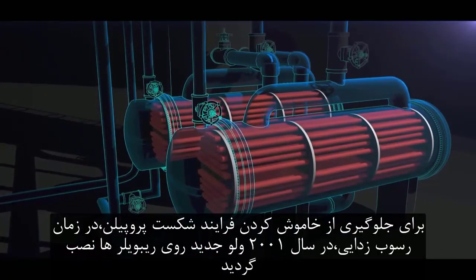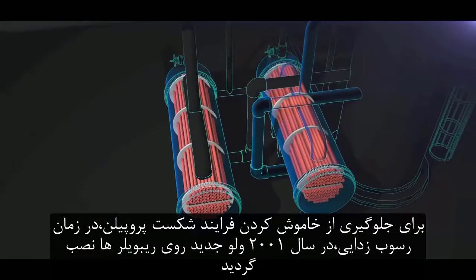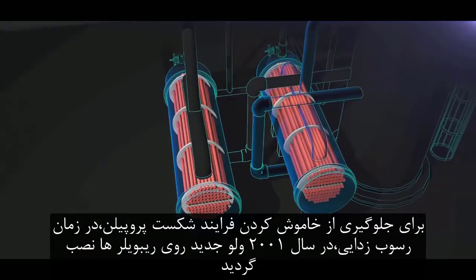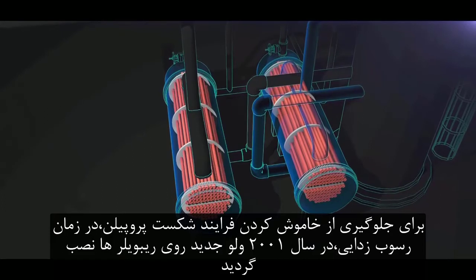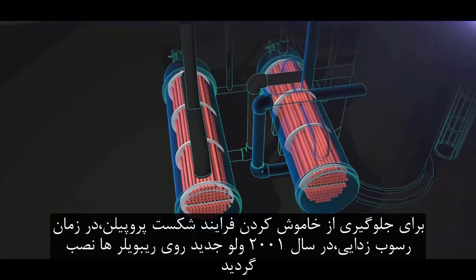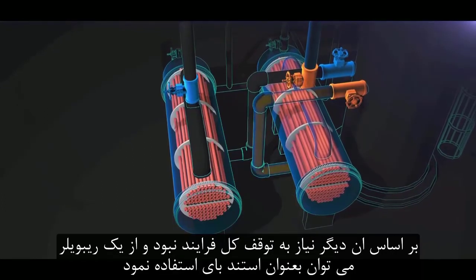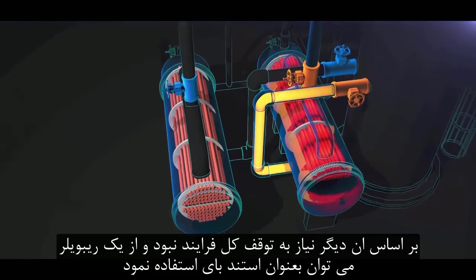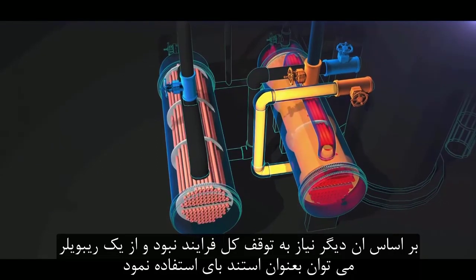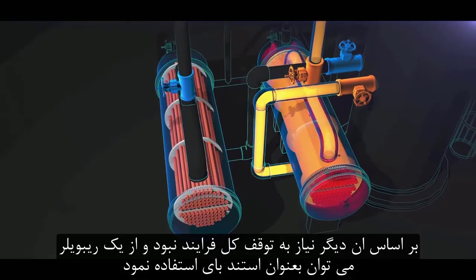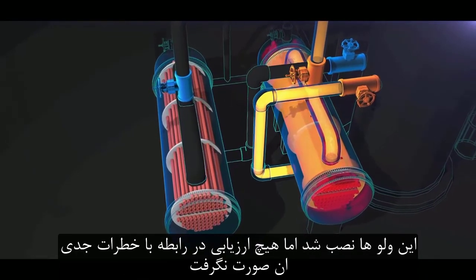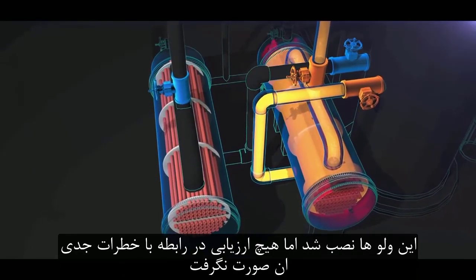To prevent shutdown of the propylene fractionator each time the reboilers needed to be cleaned, in 2001, new valves were installed on each reboiler to allow for operation of only one at a time. The other reboiler is on standby, clean and ready for use. But unforeseen at the time, these valves introduced a serious hazard.